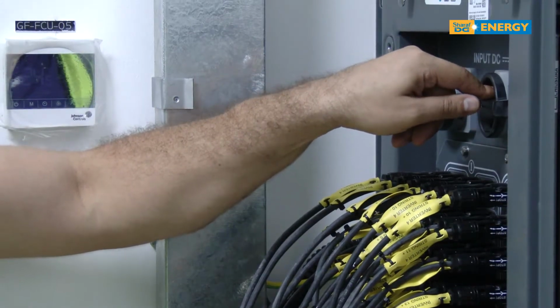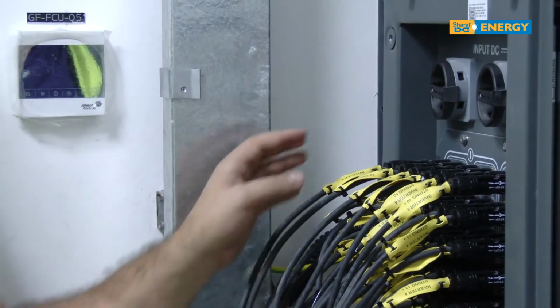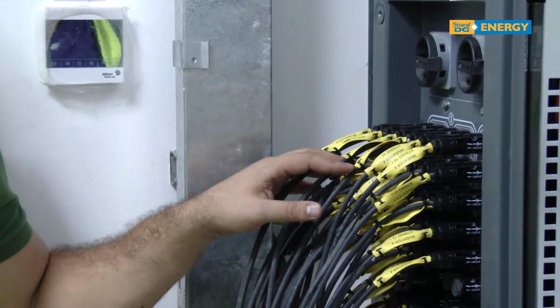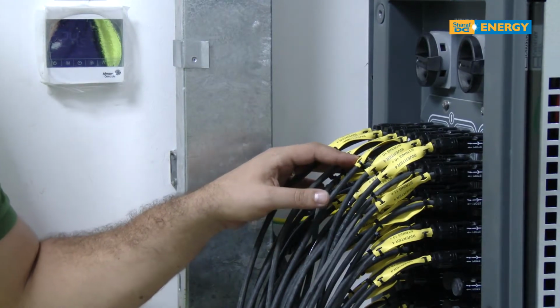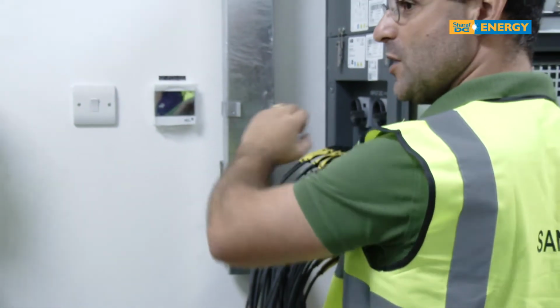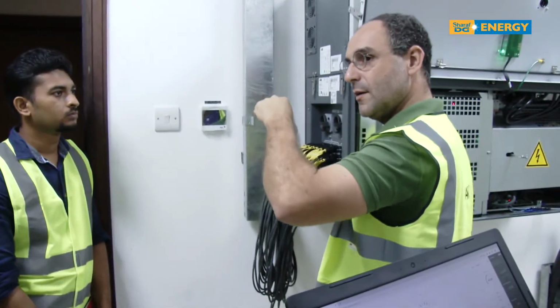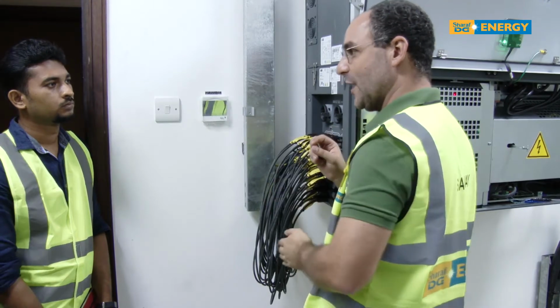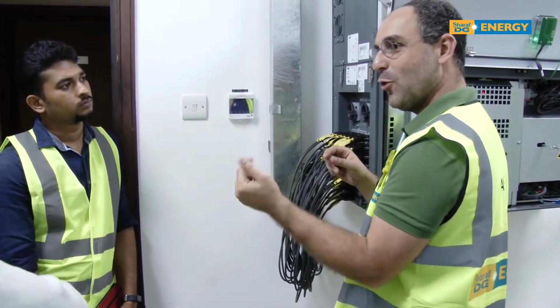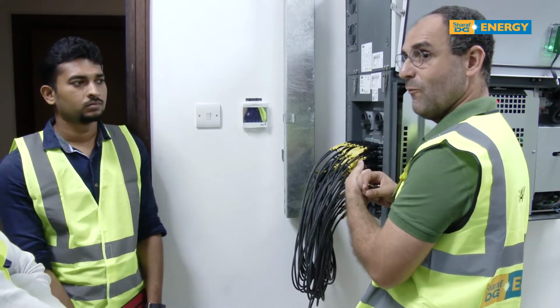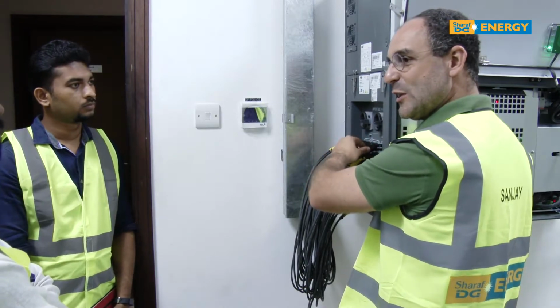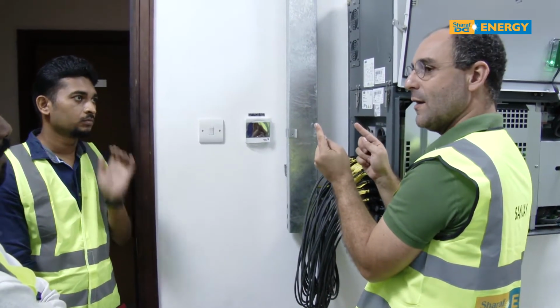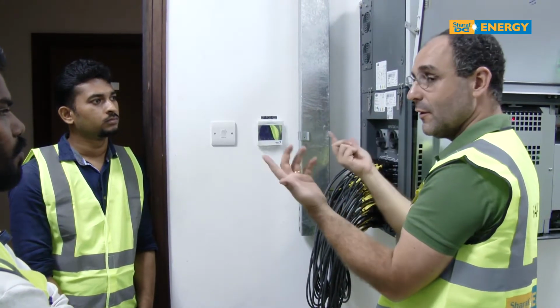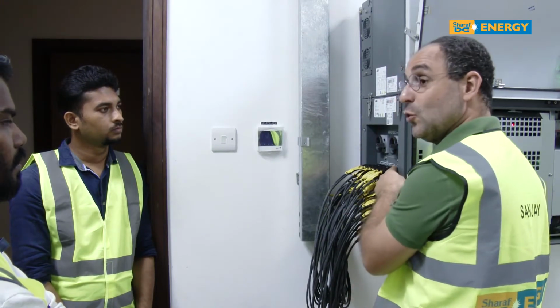You are only authorized to touch, remove connectors, and open stuff if you are sure the inverter is off. Because if the system is under load and you come here with the switch and remove it, since there is current flowing, imagine a pipe of water. If you put a grinder on a pipe with water running, what happens? Some water will come out. Same with electricity, you get an arc. If I plug this and push it slowly, I will have an arc, and these arcs can go big and could catch you, jump at you, whatever. At the same time, if you do that, you will lose the warranty on your machine.